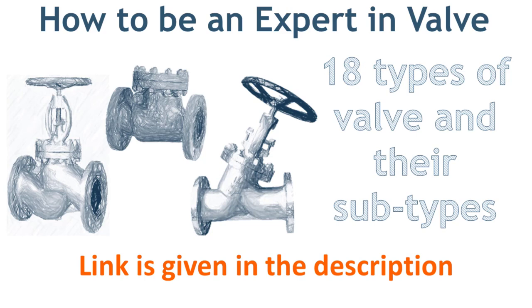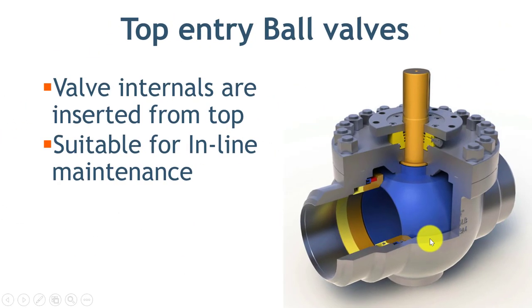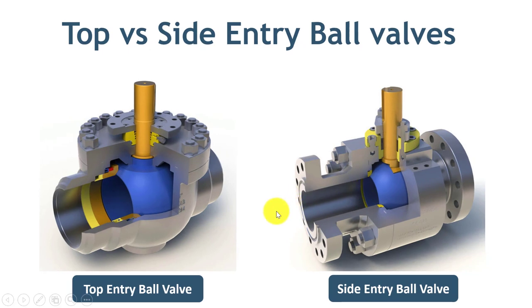On this slide, you can see the top entry type ball valve. The benefit of this type of valve is that you can repair it without removing it from the pipeline. You just have to remove the bonnet and all the valve internals are accessible to you. Looking at both top entry and side entry ball valves together, you can easily understand why the top entry ball valve is maintenance friendly.